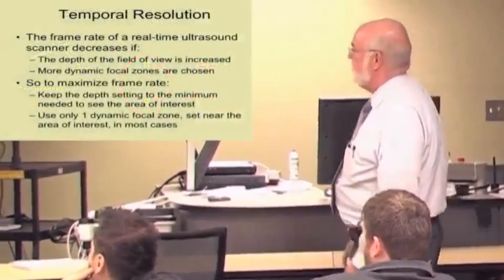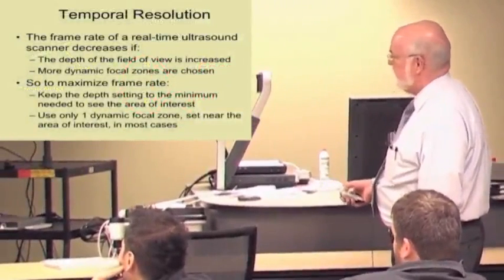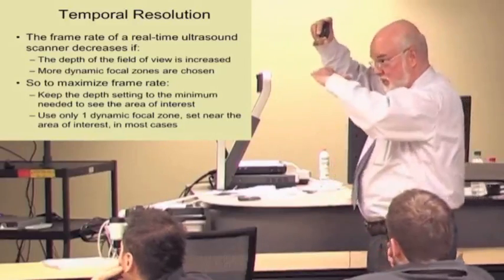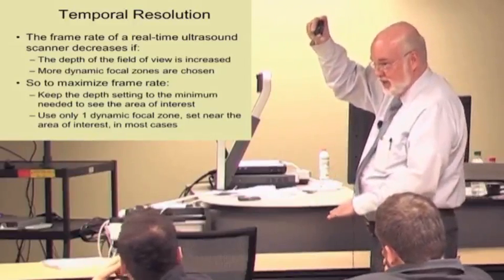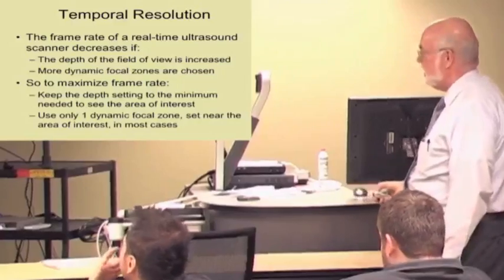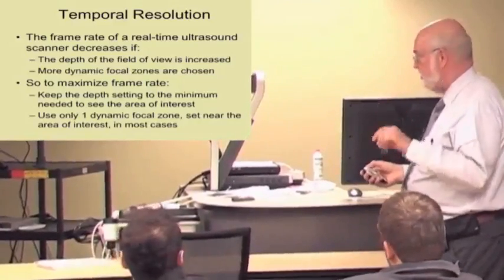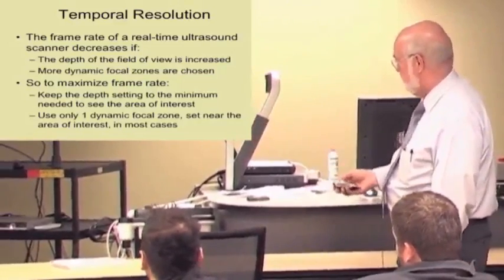Temporal resolution, well, that's just basically the frame rate. To maximize the frame rate, keep the depth setting to a minimum. If you're looking at something that's this deep in the body, you don't want your depth setting this deep because you're just wasting the computer's efforts. And the same thing is use only one dynamic focal zone if that will do the job, set to the area that you're really interested in instead of multiple ones because both of those things slow down the frame rate.